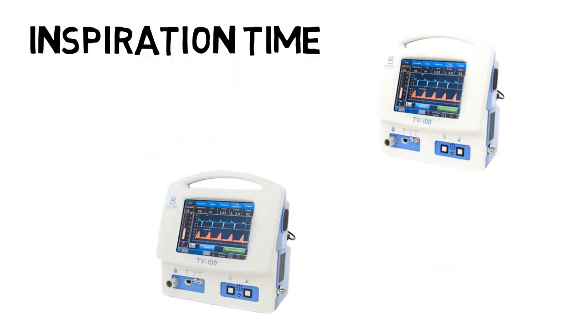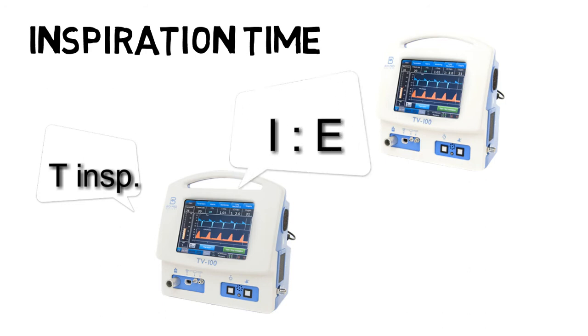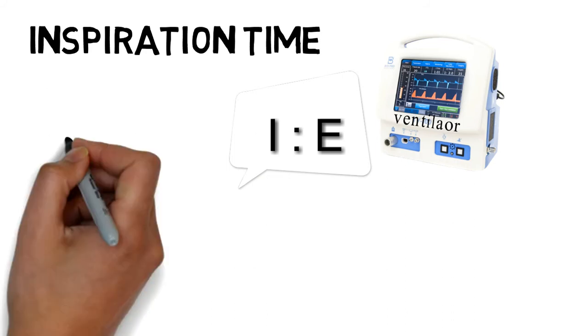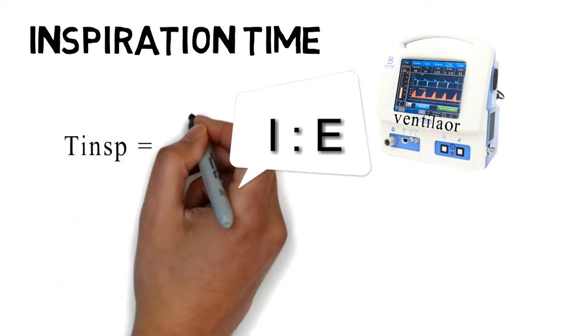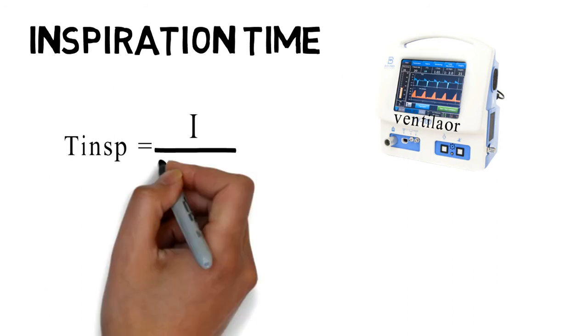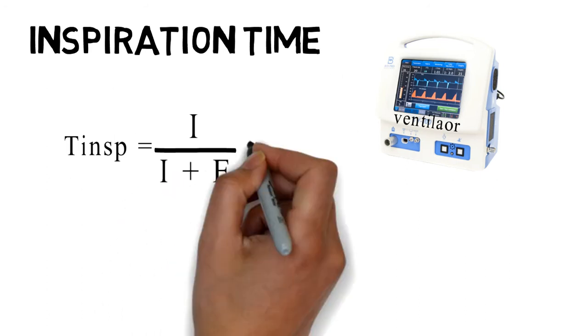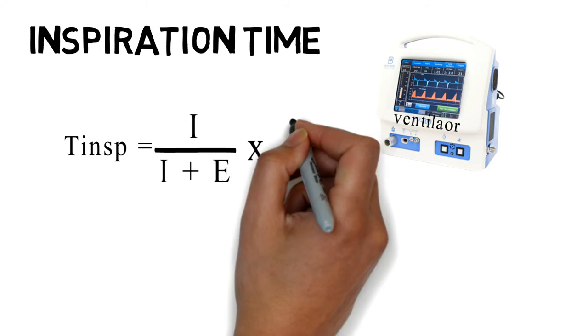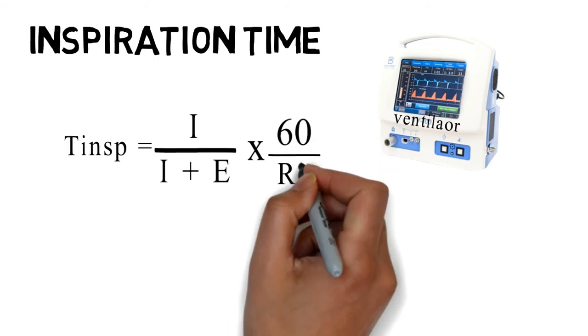The next is inspiration time. Most ventilators offer either the ability to change the absolute inspiratory time in seconds, or the ability to change the ratio of inspiratory to expiratory time. What can we do if we are given the desired inspiratory to expiratory time and have to set the inspiratory time? We have the formula for the inspiratory time as I divided by I plus E, multiplied by 60, divided by RR.